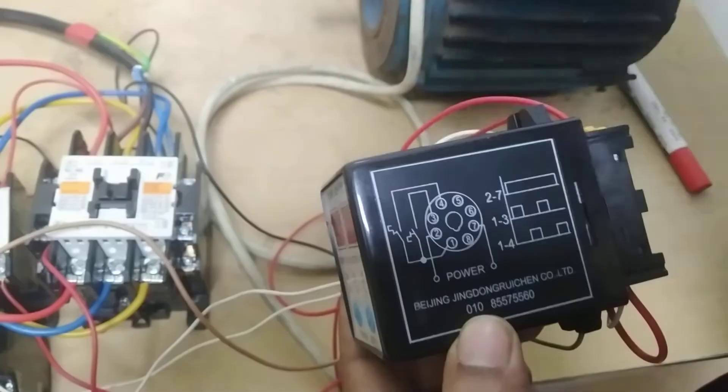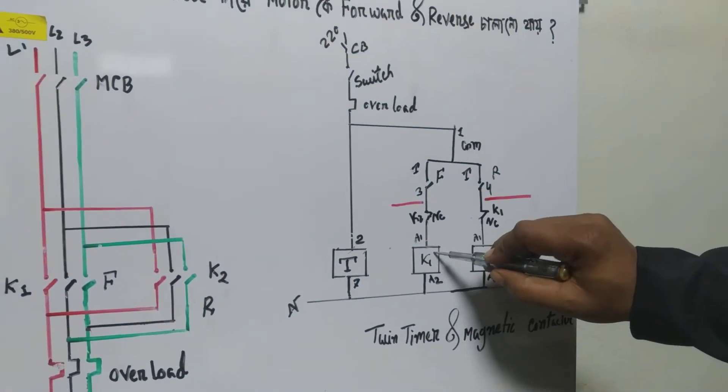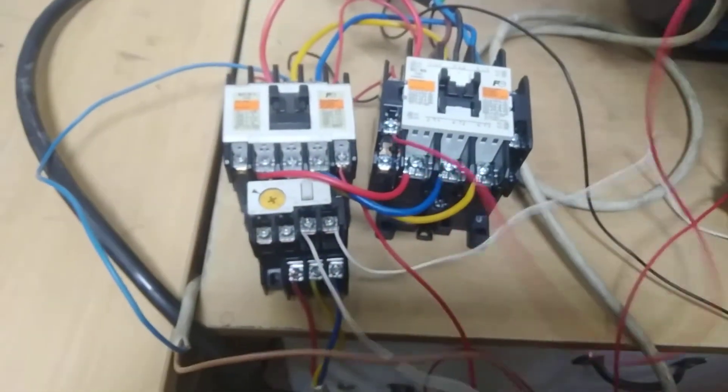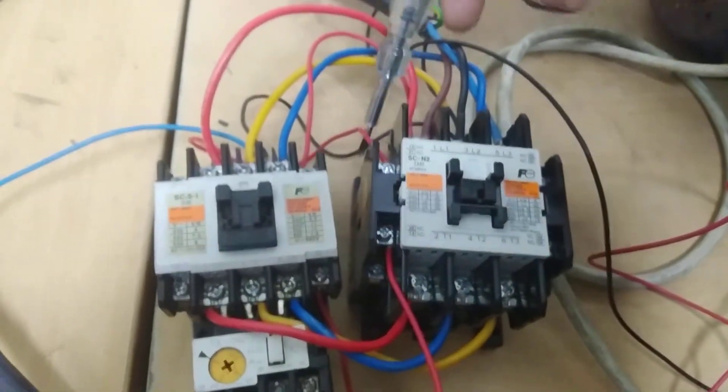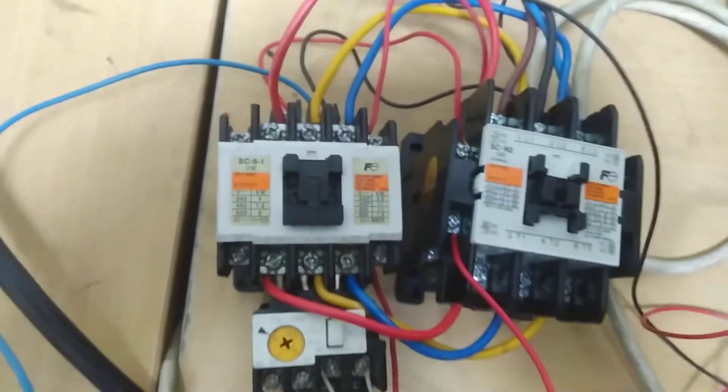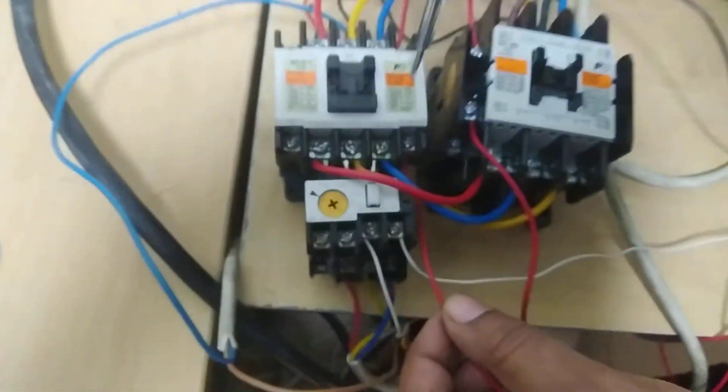This connects to the forward magnetic contactor K1 coil. The reverse magnetic contactor K2 has a normally closed contact from terminal 4 for interlocking between the contactors, preventing both from activating simultaneously. The reverse contact goes to K2.